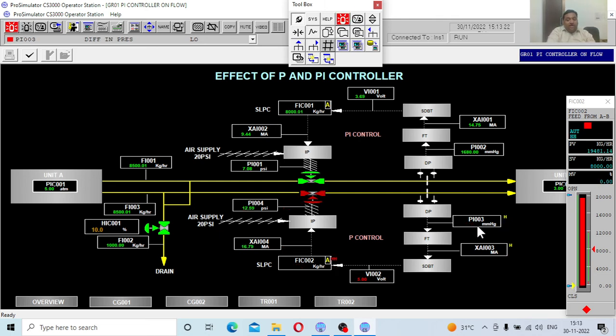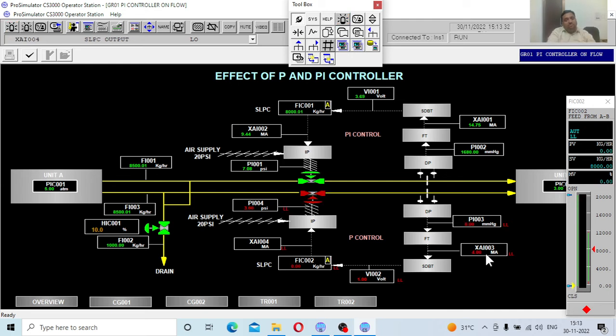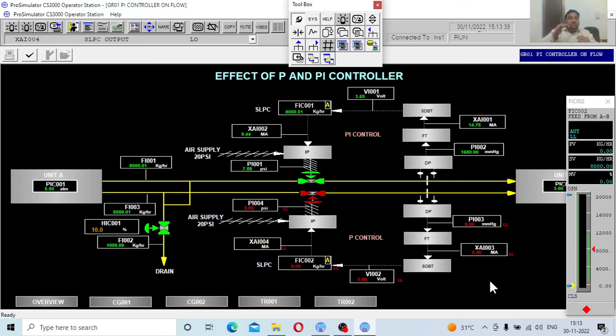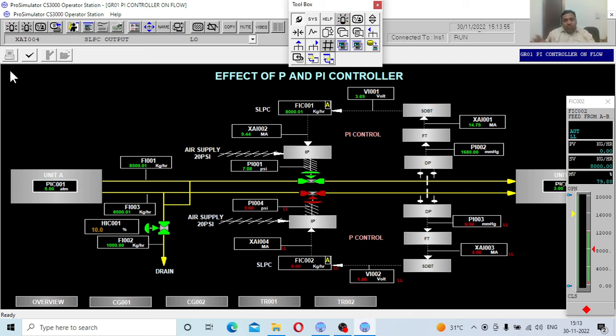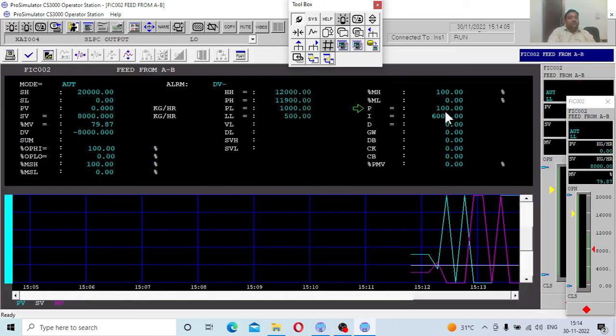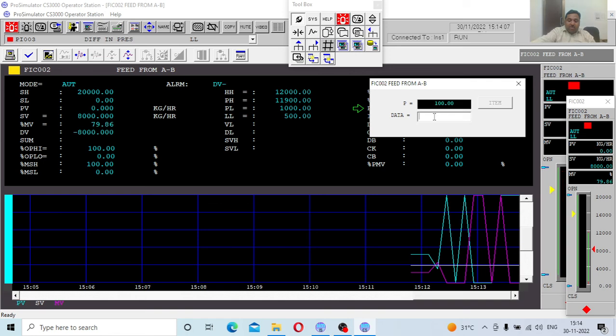You can see red alarms being triggered — for example, differences in pressure, high and low alarms for PI-003. The value is deviating beyond limits: the maximum value of the current is 20 mA, and the signal is hitting that limit — the valve is opening and closing rapidly trying to reach the set value, creating low and high levels in all measurements. The flow transmitter gives 4 to 20 mA errors, and the signal distributor gives 1 to 5 V errors, meaning the system is deviating far beyond normal. The operator must immediately see what is happening and reduce the P action by increasing the number.